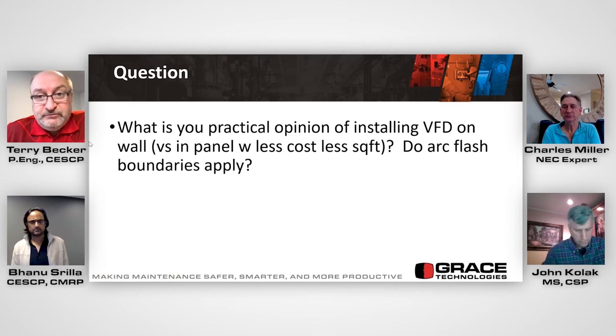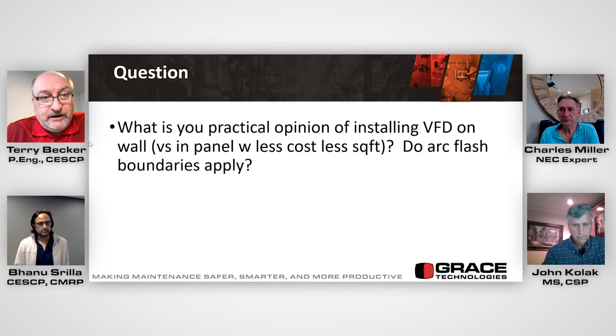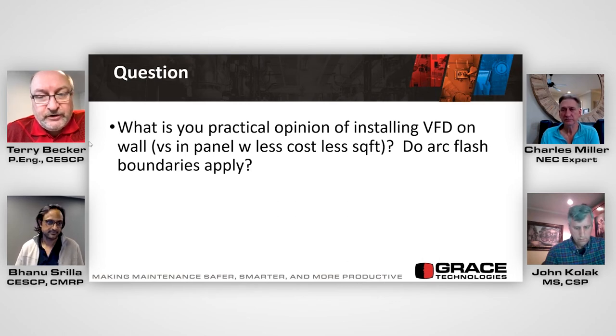These operators need to read the HMI. They may be authorized to change the speed with the HMI. There's no arc flash hazard to do that. This is proliferated everywhere, and we got to be real careful here, because this is one of the myths and misinformation I communicate: energized electrical equipment isn't inherently going to have an abnormal arcing fault on it unless there's some precondition that will make a higher likelihood of it occurring, right?